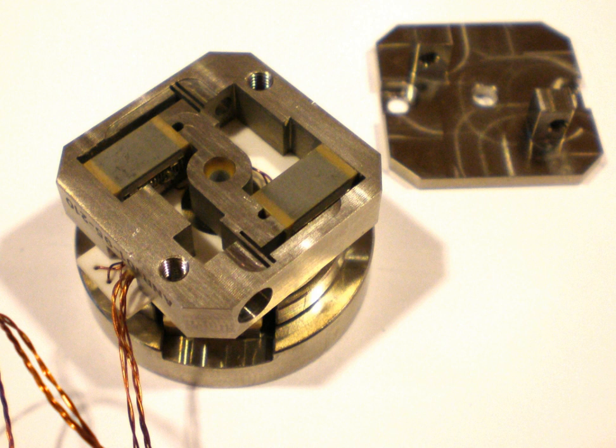However, if both locking groups are powered at rest, a normally free motor resists external force without providing any motive force. A combination of mechanical latches and crystals can do the same thing, but would restrict the maximum stepping rate of the motor. The non-power behavior of the second type of motor is locked, as the drive screw is locked by the threads on the nut. Thus it holds its position with the power off.